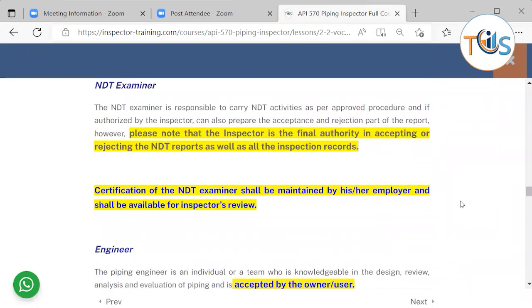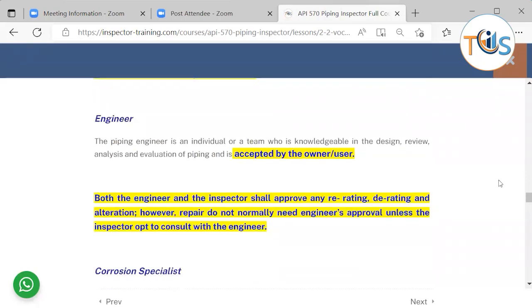The NDT examiner is an individual who is qualified to perform a particular NDT method or technique, responsible for carrying out NDT activities per approved procedure. If authorized by the inspector, the examiner can also perform interpretation — comparing results against acceptance criteria — but the inspector is the final authority in accepting or rejecting NDT reports. Certification of the NDT examiner shall be maintained by their employer and be available for the inspector's review as part of the reports and records.